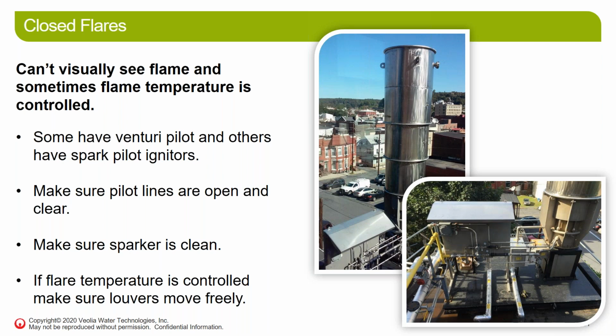Closed flares, you can't see that flame easily. You kind of have to crouch down, get underneath it, look underneath it to see that flame. But they have very similar features. Again, if it's a Varec enclosed flare, they'll have very similar controls to the open flame flares. But again, you still have to look at that pilot line, make sure your spark plugs are working. If there's a Venturi system, make sure that's clean and working. Some systems have a blower assisted pilot, so you have to check that blower, make sure that blower is working. If the flare is temperature controlled, make sure the louvers are moving freely or in the right positions.